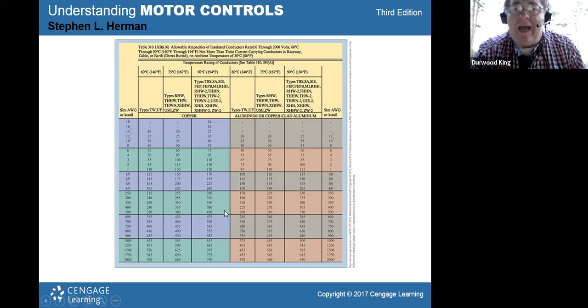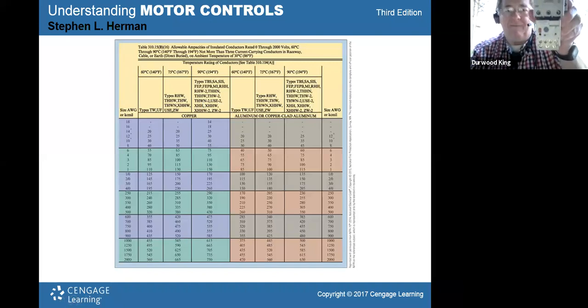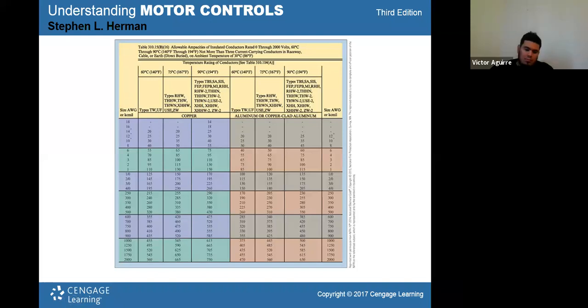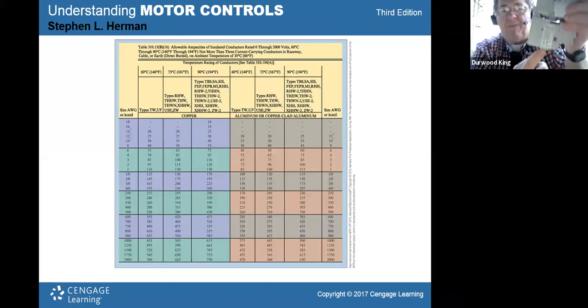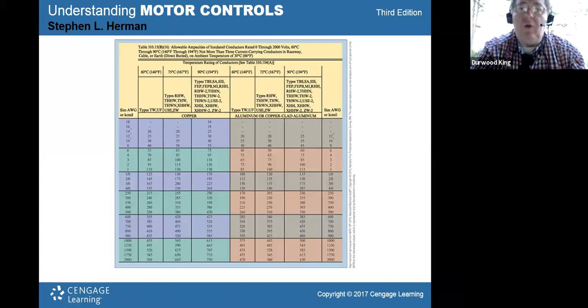Now, the first thing we've got to do, guys, is look carefully and figure out what column we're going to be in for the temperature rating of the wire. Let's give you a real scenario. See that starter I have here? Say the temperature rating says a maximum of 75 degrees Celsius on those terminals. Now, let's say you've got wire in the plant that's rated at 90 degrees Celsius. The wire can handle 90 degrees C. It's okay to use that wire.